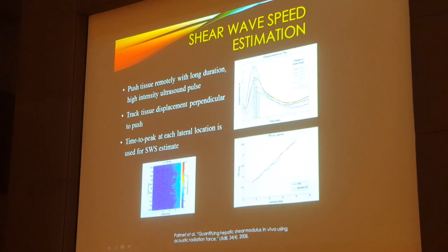And what happens is we get these series of curves, which you don't see, it's done in the back of the machine, where we use B-mode imaging to track those shear waves. So the B-mode closest to the RF pulse is going to have the strongest pulse, and it's going to curve faster. And we get this family of curves, and if we take the peak versus the time that it took to get there, we get a slope, and the slope of the line is the shear wave speed.